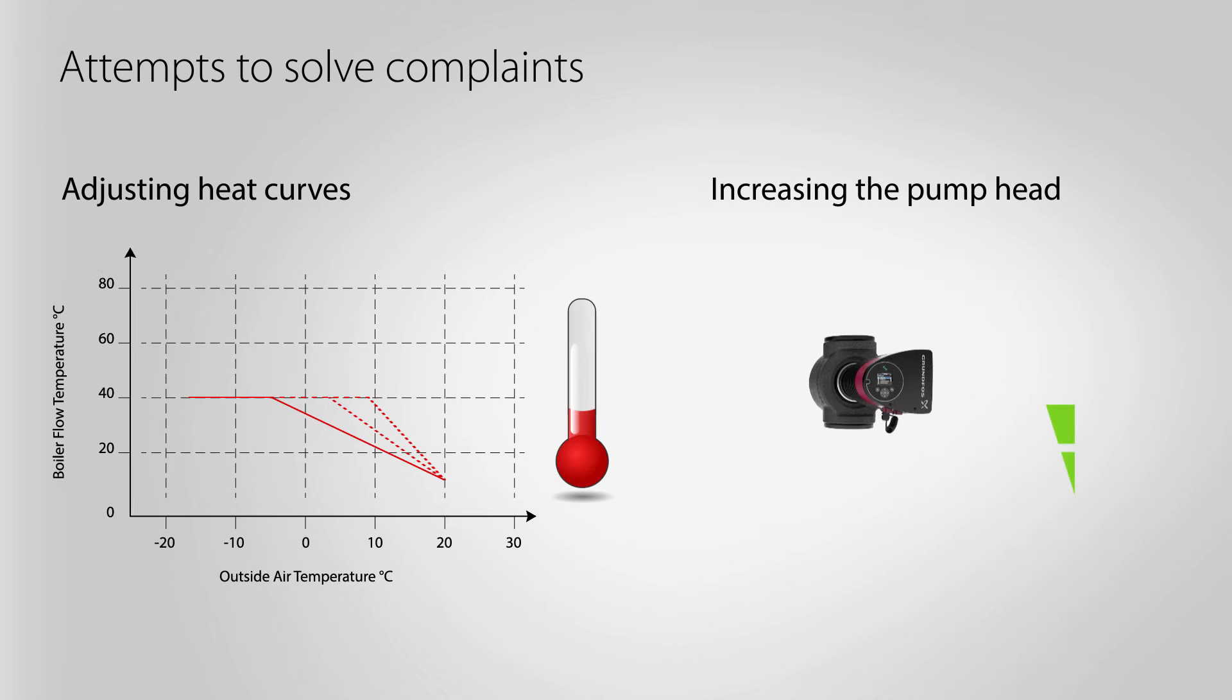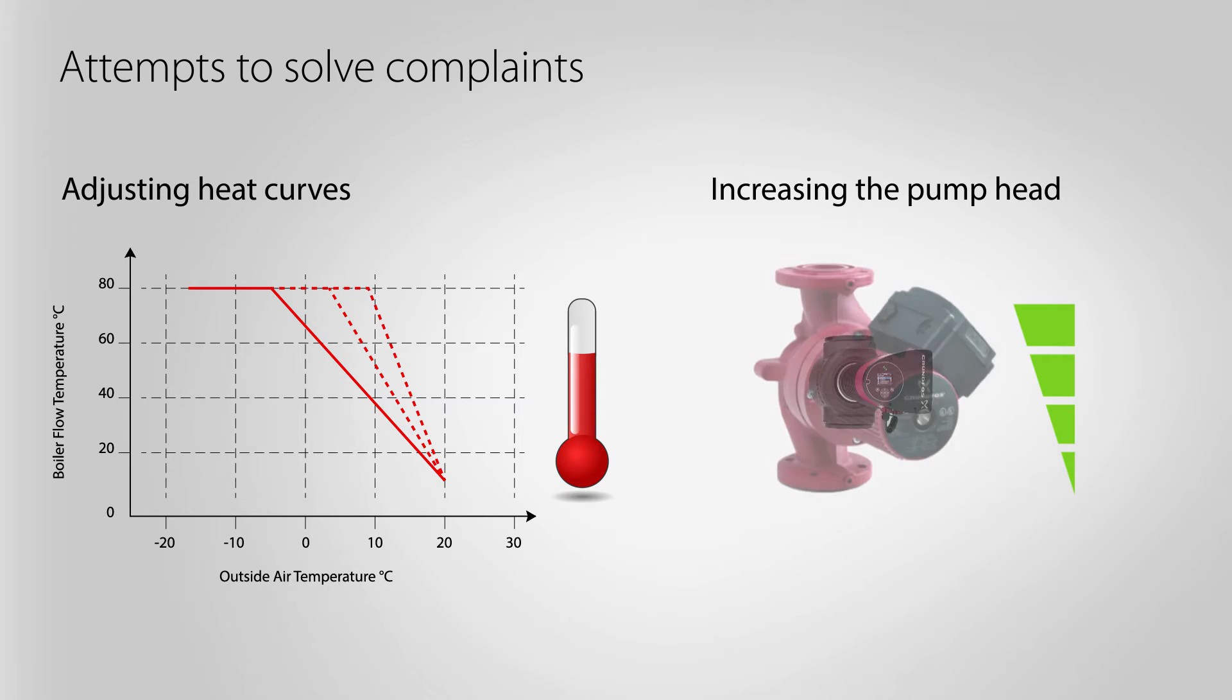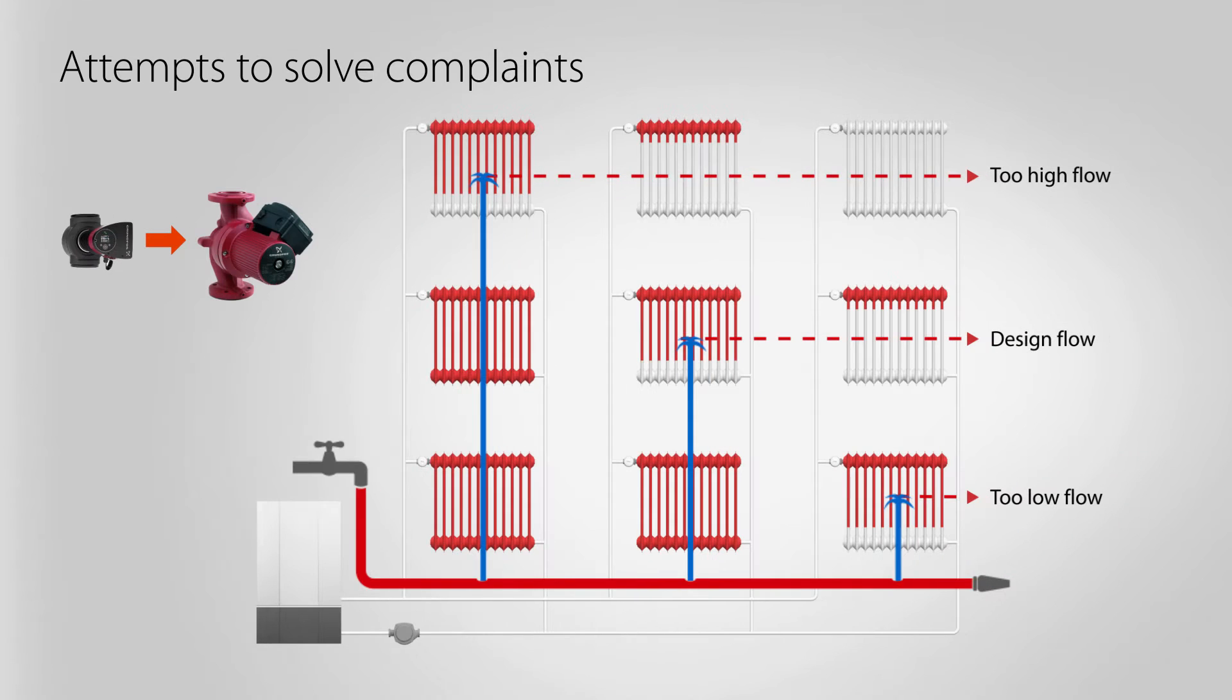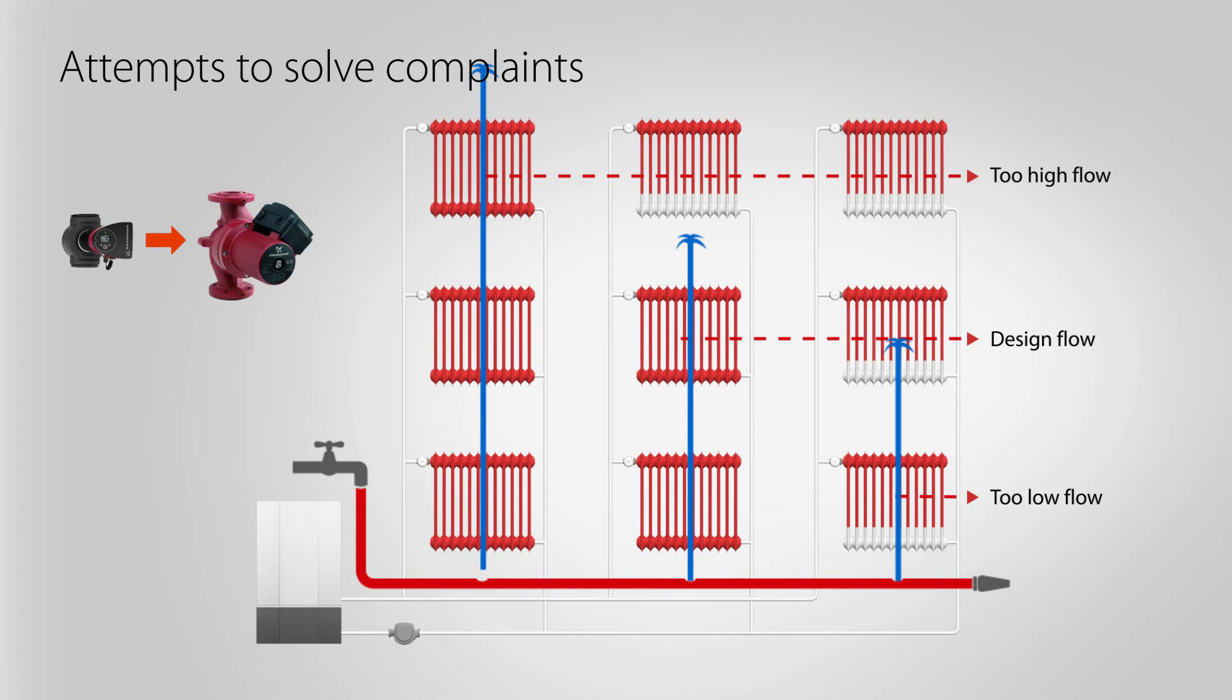In an attempt to solve the issues, often the water temperature is increased or a larger pump with a higher pump head capacity is installed. Such attempts increase further overheating, especially by radiators closer to the pump, resulting in significantly higher energy consumption. This is not a valid solution.